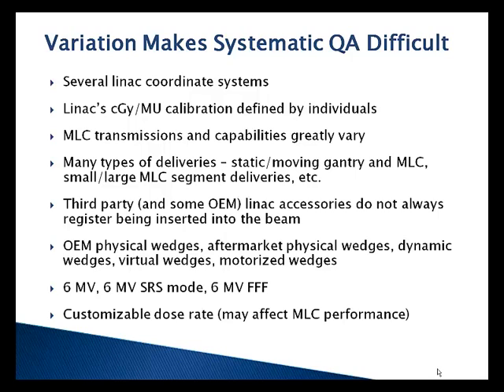And if you come tell me I did a calculation with the 6MV beam, now I have to ask, was that 6MV traditional? Was that SRS mode, which has a smaller flattening filter? Or is that flattening filter free, which we've taken the flattening filter out? And all three of those have completely different dosimetric capabilities. So you can't hand me a plan that says 6MV, 200 MU, and expect me to have any idea how to calculate that, because I don't know what 6MV that is. I don't know what centigray per MU factor your clinic uses. It's a very interesting problem.